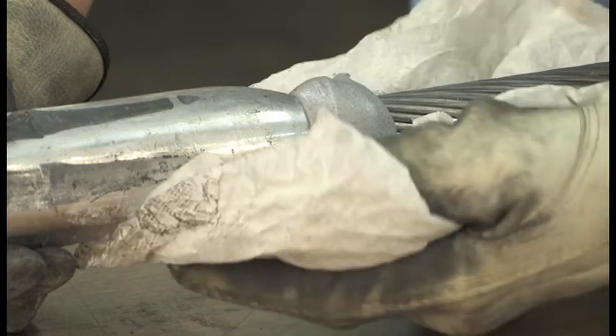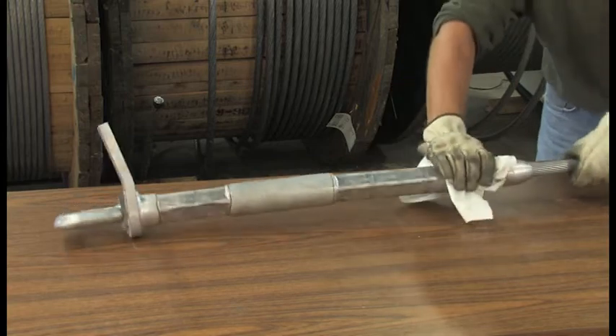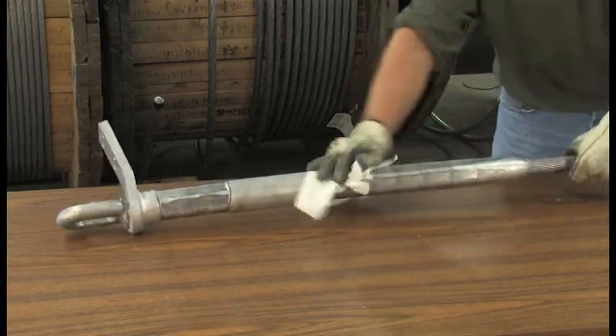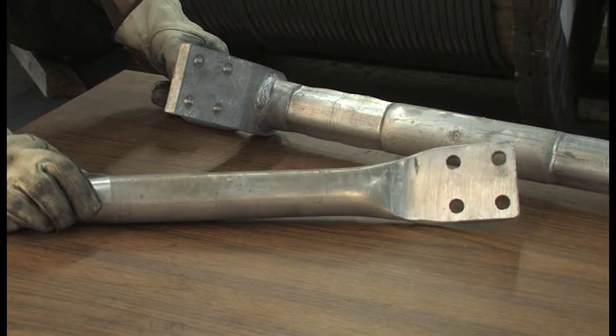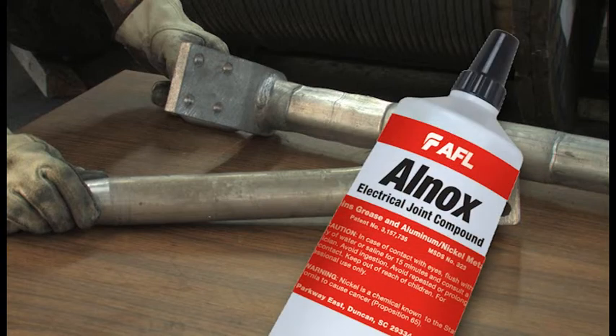Once you've finished the compressions, wipe off the excess compound. The outer sleeve should also be wiped clean. The installation is complete and should look like this. The dead end can now be connected to the insulator string and the appropriate jumper connectors can now be installed. The terminal pads are to be brushed along with the use of AFL's Alnox electrical joint compound between the terminal pad and the dead end. This will ensure a good electrical connection.